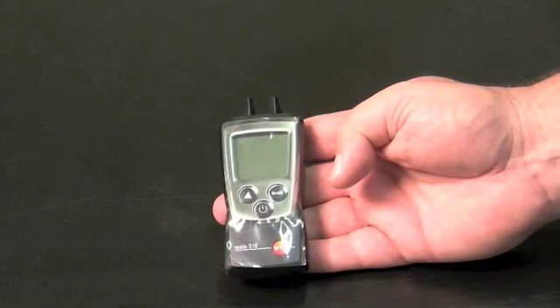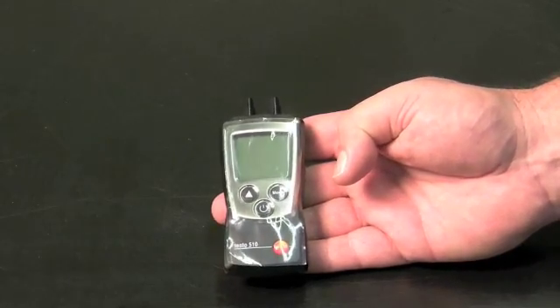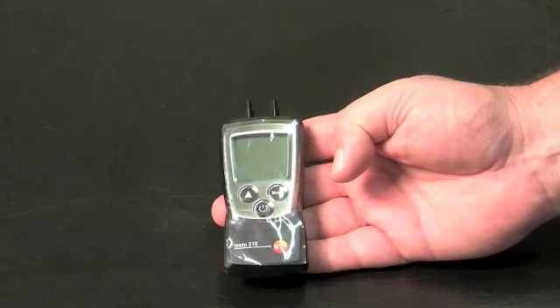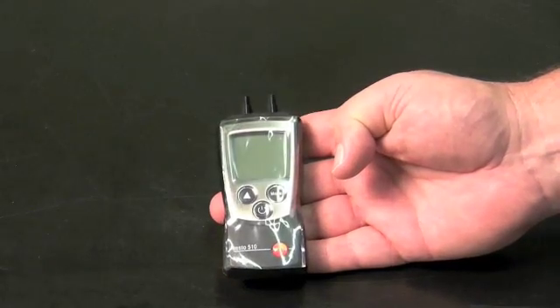To check differential pressure, you need the right tool for the job. You can use anything that will measure differential pressure, a magnehelic gauge, a slack tube manometer. The tool we like to use is this Testo 510.